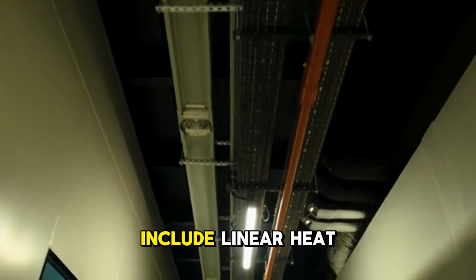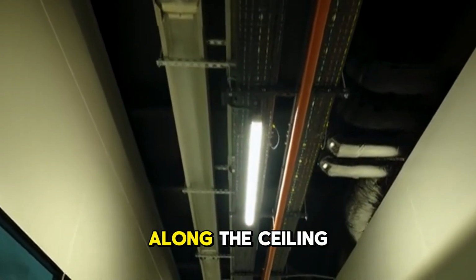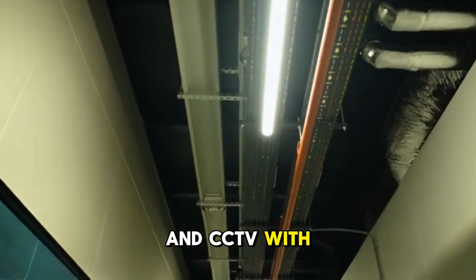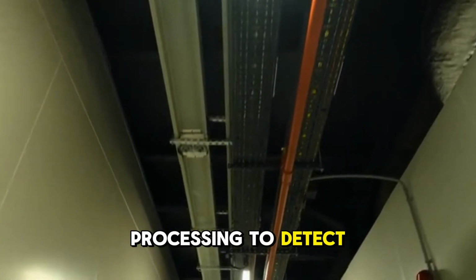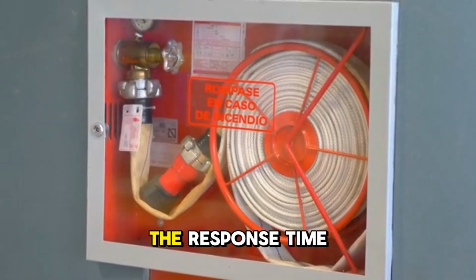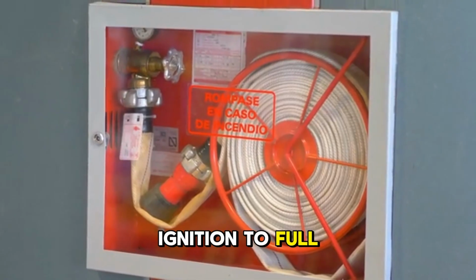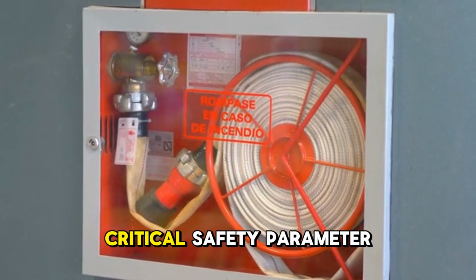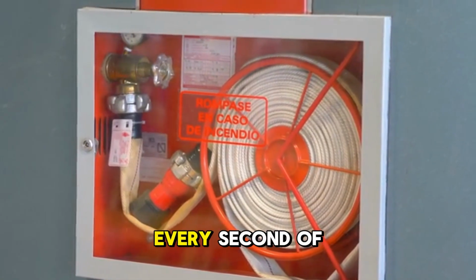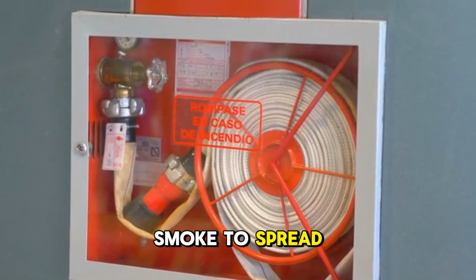Detection systems include linear heat detection cables along the ceiling and CCTV with automatic image processing to detect smoke signatures. The response time from ignition to full emergency mode is a critical safety parameter. Every second of delay allows smoke to spread further.